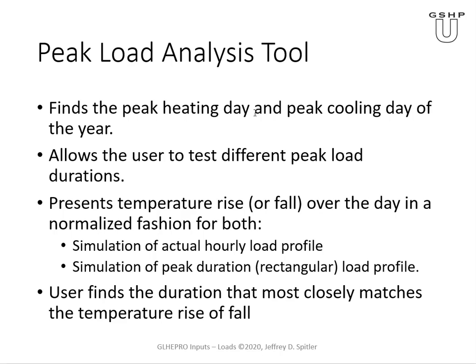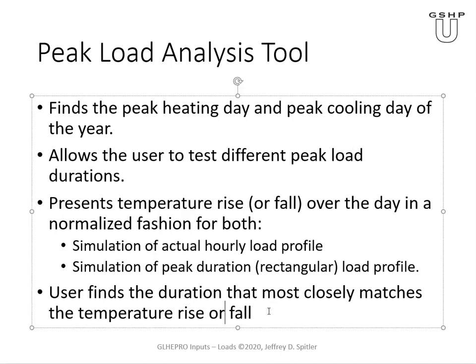So it calculates the normalized temperature response, and then it does it for both simulating an actual hourly load profile for that day and then a rectangular load profile. And then the user uses that to find the duration that most closely matches the temperature rise or fall over the day. We'll have an example later. Okay, we're going to pause there.